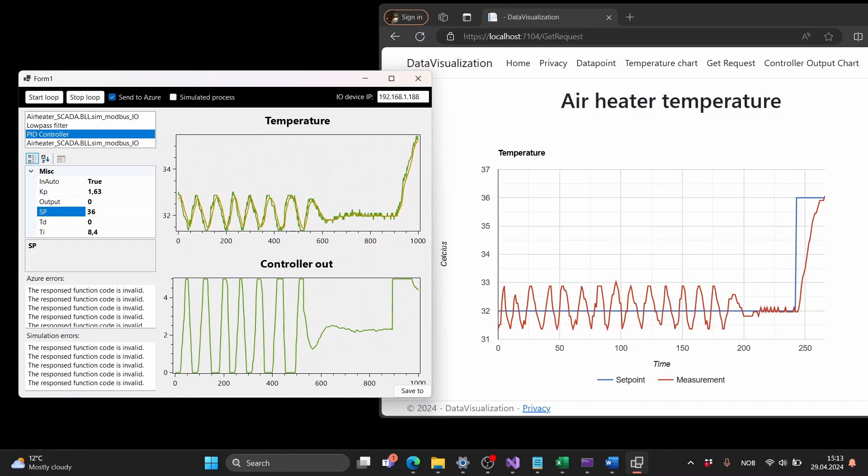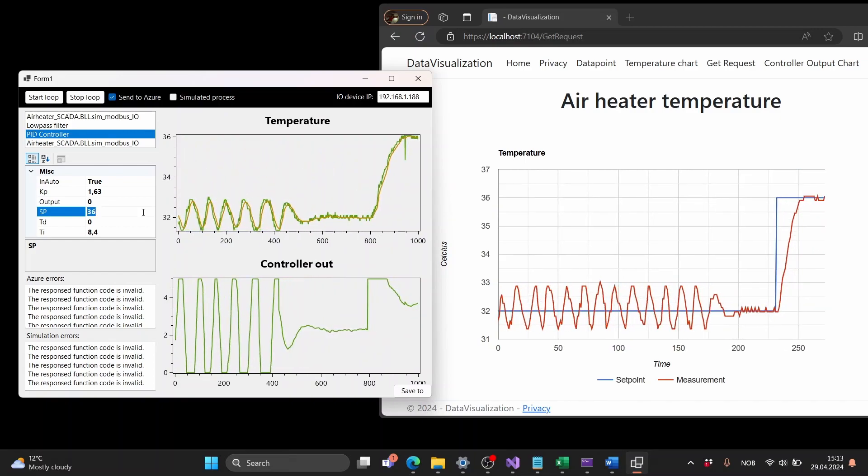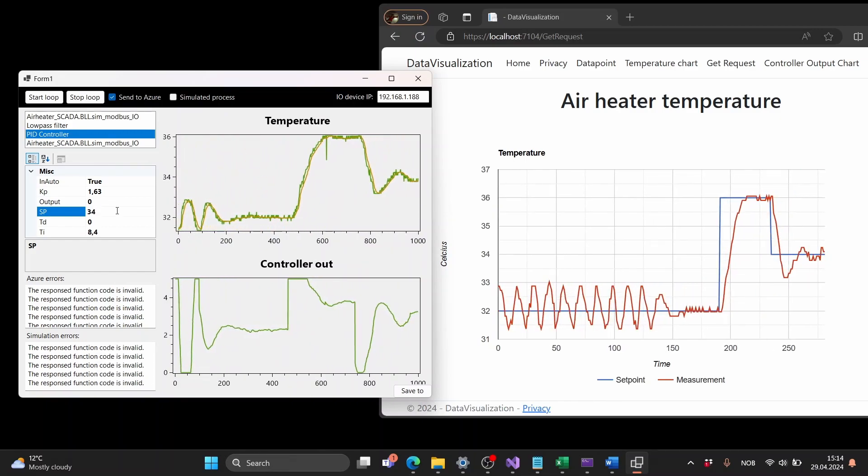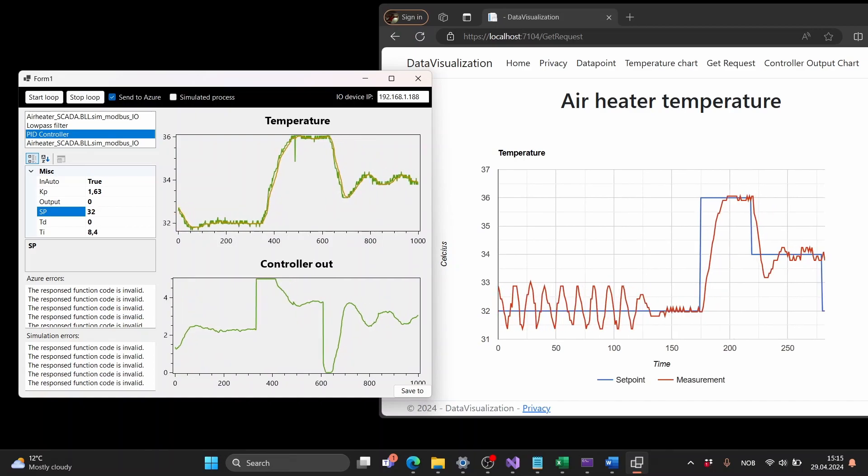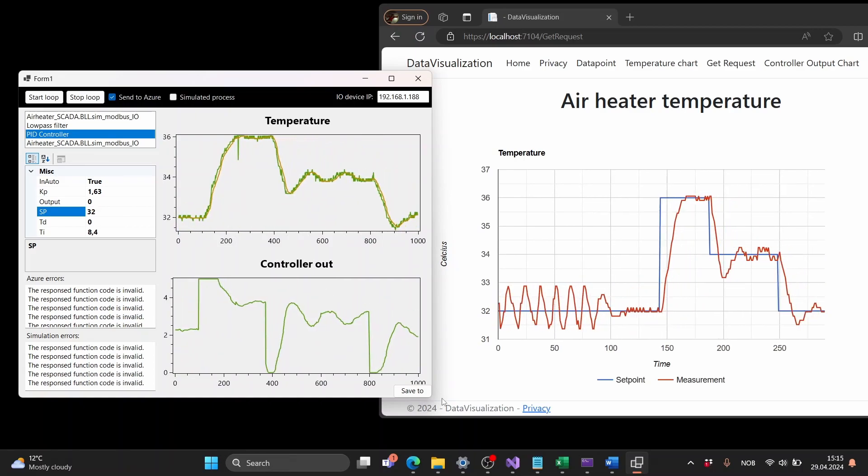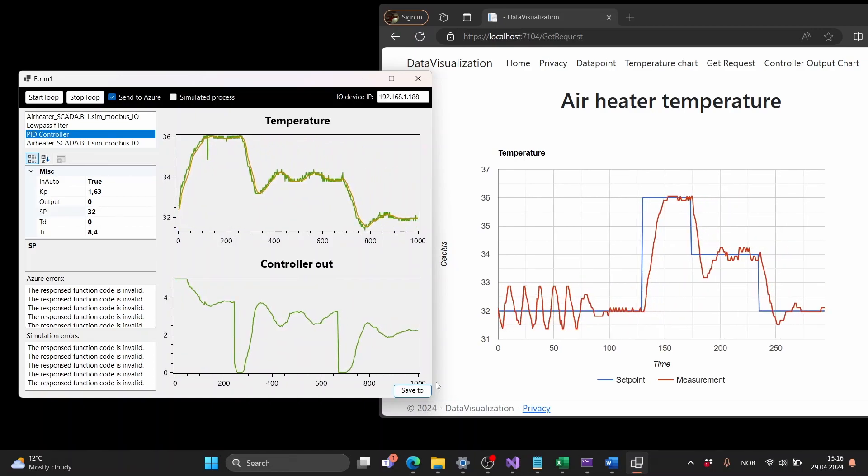As you see the temperature goes to the set point after a set point change and there are no oscillations so these parameters seems to work good.